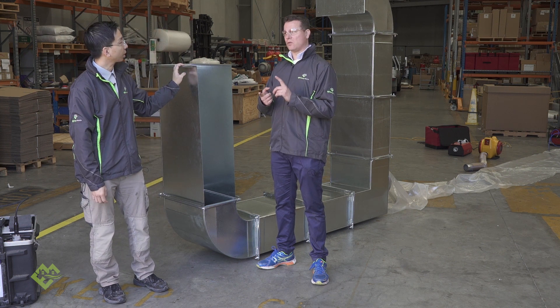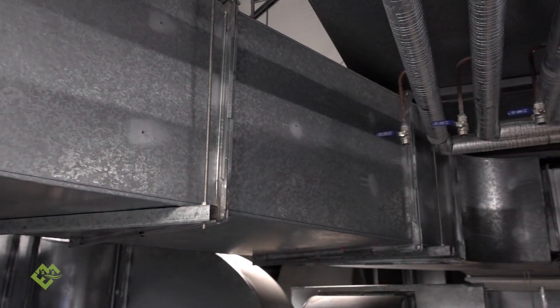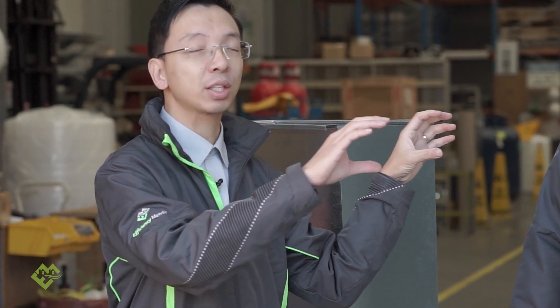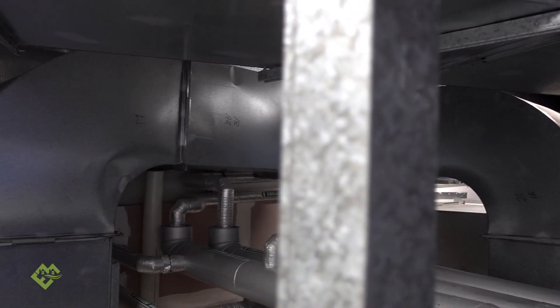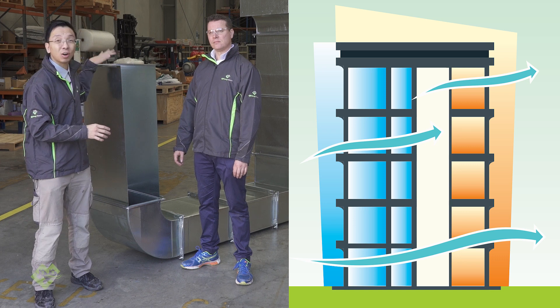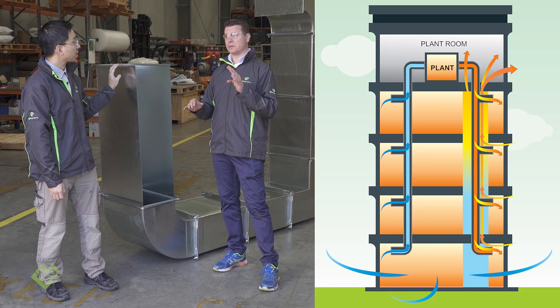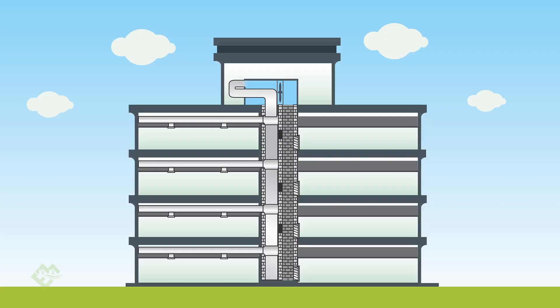There are also other implications for the building envelope. Ductwork is usually connected directly to the air handling unit, which is either on the refuge floor mid-rise or in the roof plant room — areas that are open and exposed to wind. When you bring wind pressure into the picture the situation becomes much more complex. Many masonry risers housing sheet metal ducts connect all the way to the top, making them a major weak point in the building envelope.